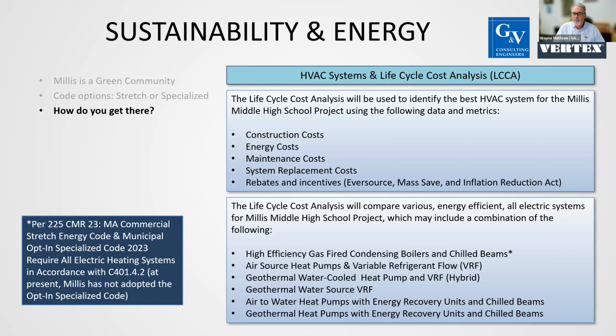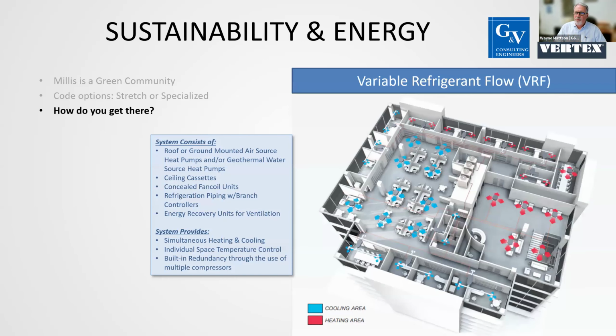And then Chris, if you jump down to the next slide - one of the systems you see at a lot of schools now that's electrically based is the variable refrigerant flow system. This illustrates how it works: areas with blue arrows are calling for cooling, areas in red are calling for heating. What happens is heat is extracted from the rooms calling for cooling, and that provides the heating source for adjacent rooms. The system consists of ceiling cassettes or ducted fan coils that you don't see - you just see normal diffusers. It's all interconnected refrigeration piping that runs outside to a group of air-cooled condensing units. A couple slides down I'll show you a picture of what they look like - you've seen them, they're everywhere now.